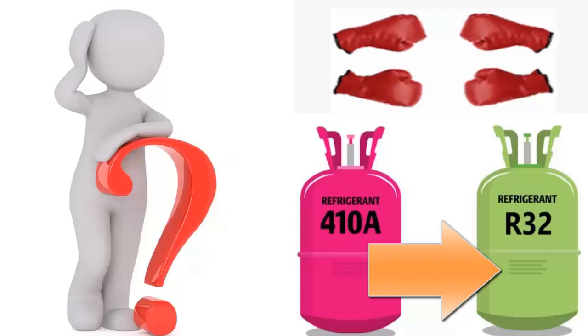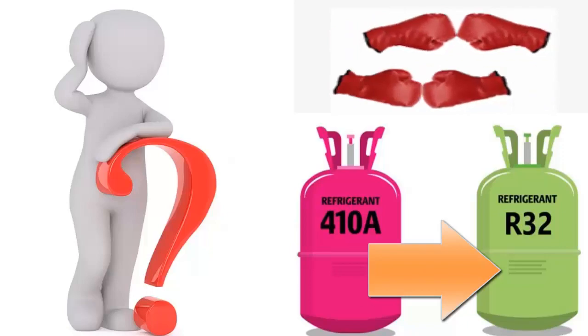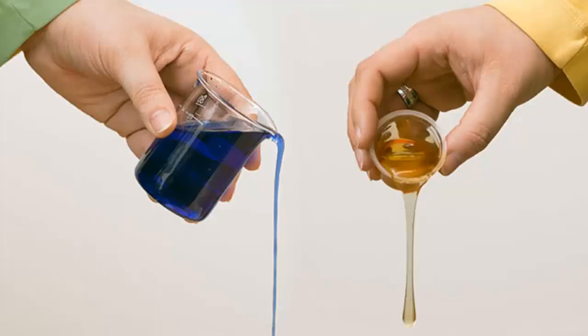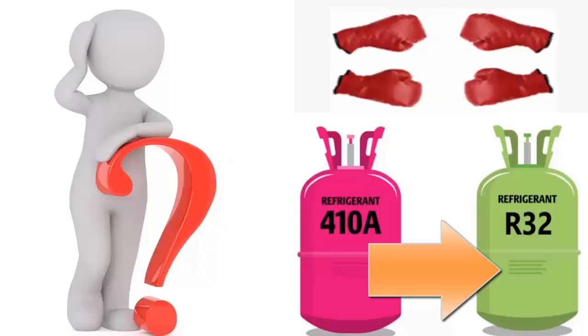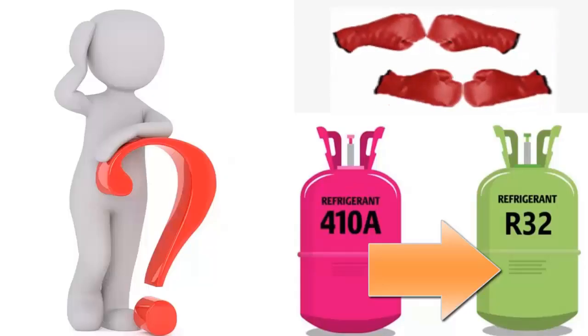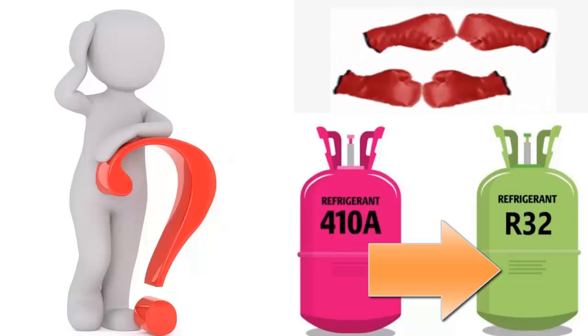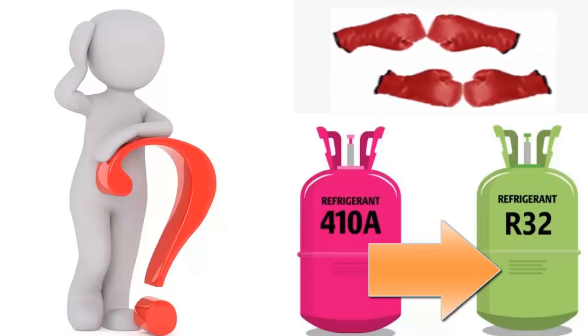1. Both R-410A and R-32 use POE oil, but due to their solubility, POE oil with R-32 tends to have a lower viscosity compared to POE oil with R-410A. This is why replacing R-410A with R-32 can impact lubrication efficiency in certain cases.